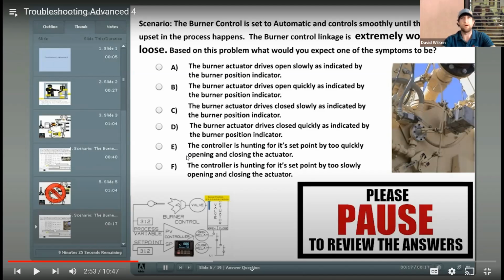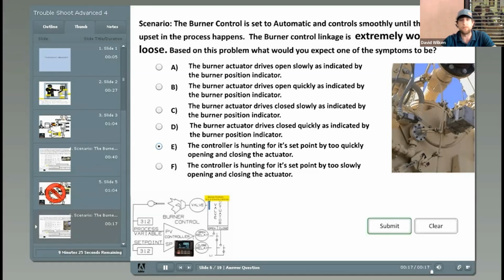Or it's just going to, you know, like this much movement didn't actually move any. So now I'm going to double that movement or whatever. I believe it's going to be quickly because you're just going to not be hitting what you're aiming for. So you're just going to be shooting all over the place. The correct answer is E. The controller is hunting for its set point by too quickly opening and closing the actuator.